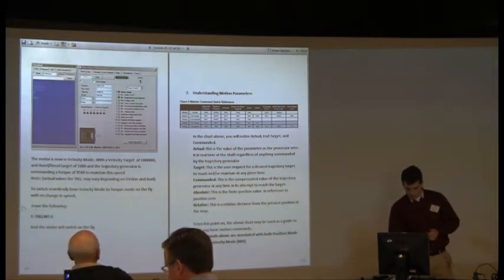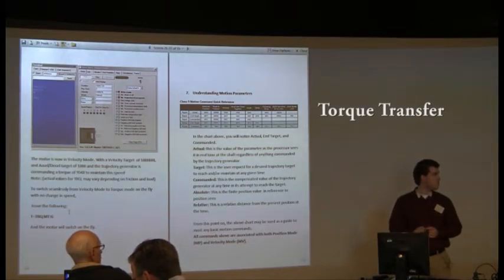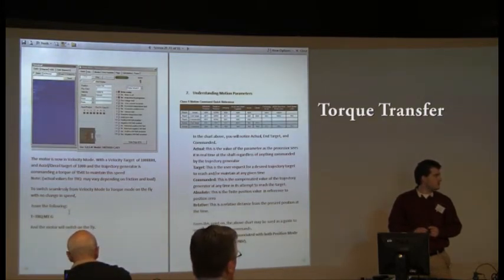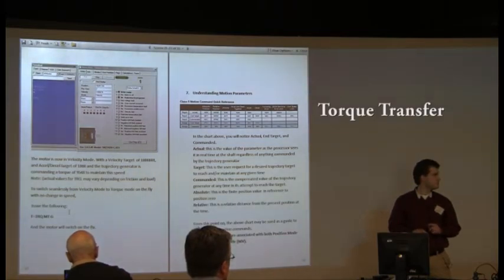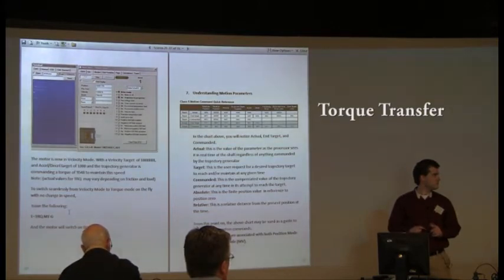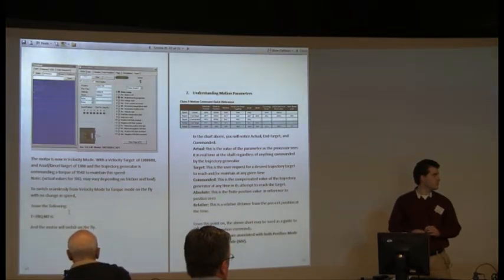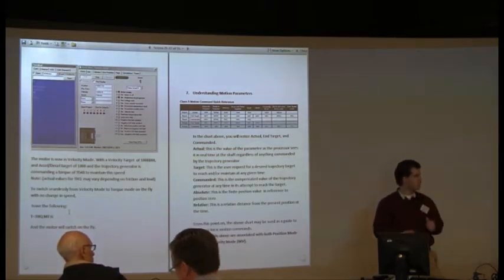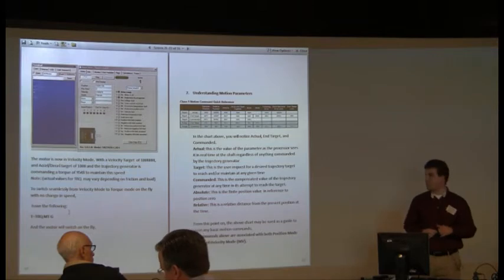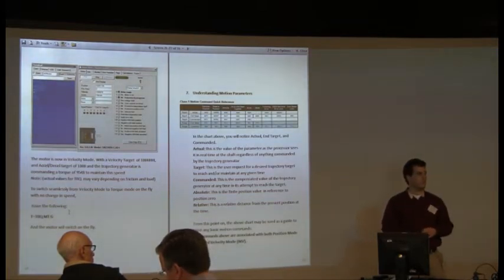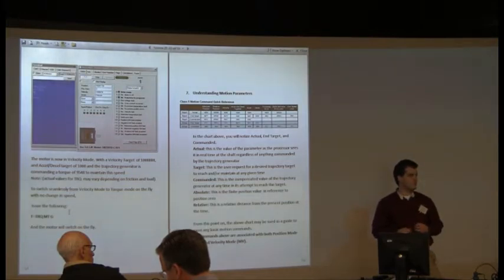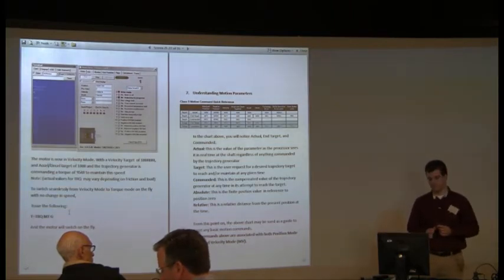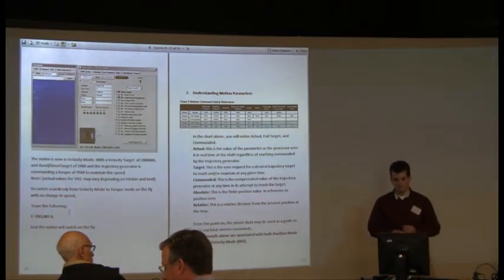The other thing is what he's mentioning here, this torque transfer is not something that's typical. This is any time that somebody wants to go in velocity mode or position mode up to a point and transfer and hold the exact same torque that they were holding when they pressed against the part. It gives them no bounce, no stutter in speed, no nothing. That's extremely valuable for guys that are pressing or holding down either nut runners, bolt runners, screw tighteners, or pressing, running plastic caps down on bottles. This torque transfer is very unique because it truly takes the exact PWM commanded and maintains a constant torque out through the transition and prevents you from having a position error or a velocity error when you do this. So it's a very unique feature that not many controllers have.